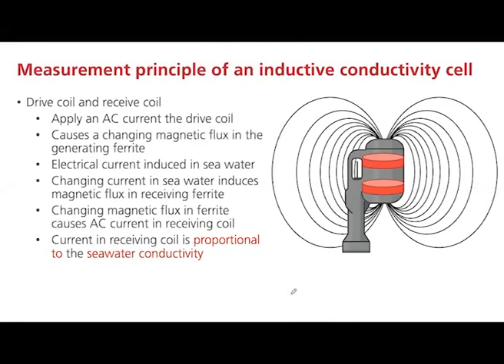Now, to go a little bit more into how these things work. Inside the cell there are two coils. This would be a ferrite ring, and you can imagine a wire loop coiled around it. There are two of them: a so-called drive coil and a receive or pickup coil. What we're going to do is apply an AC current to a drive coil. Let's just call it this one; it doesn't matter which. That generates a magnetic flux in the ferrite itself, in this circular ferrite, which in fact induces an electric field in the seawater, and that field drives a current.